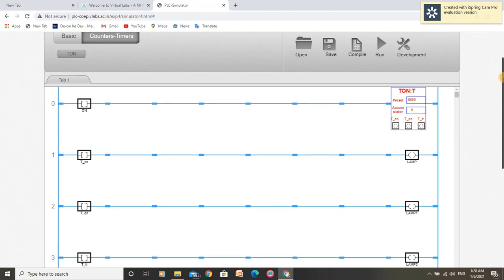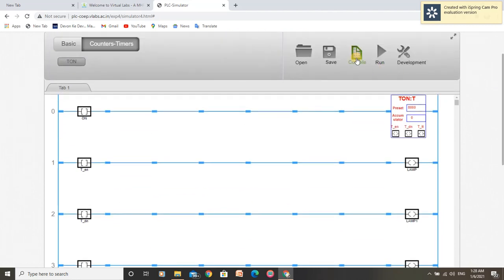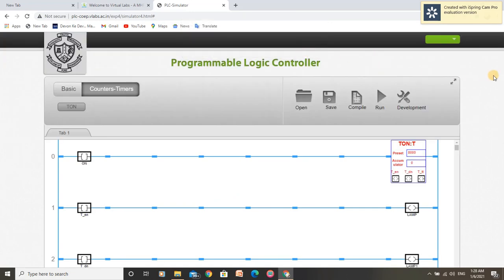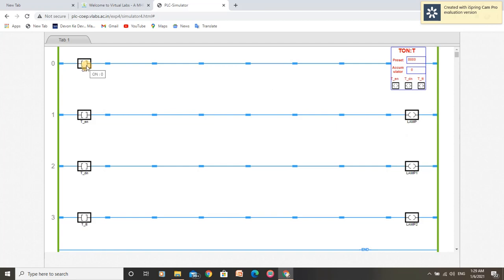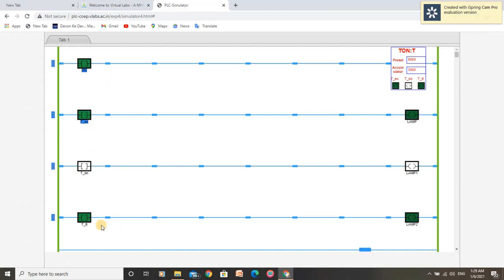Our ladder program for the on delay timer application is completed. Let us compile this program and run it. Now our program is in run mode. Let us see what happens if I toggle the on delay timer input button. We can see our enable bit is on and timer timing bit is on, as the timing operation is in progress. As our timing operation is completed because the accumulator value reached the preset value, the done bit is on.